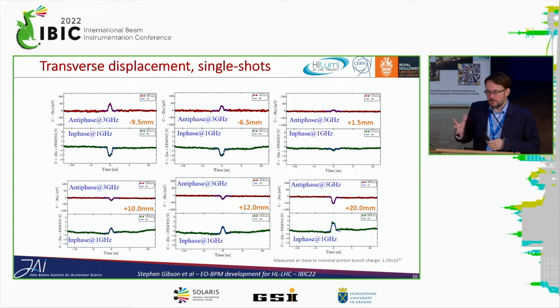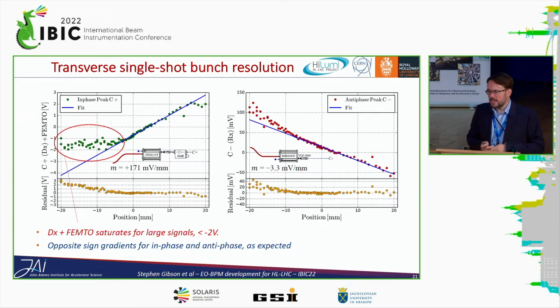As you get very close to the pickup, you actually start to see signs of effectively saturation, where the bunch is causing such a field inside the pickup that it's causing an over-rotation of the transfer function. So this is why it's distorted at the very last one, because we've got almost too much signal for what we want. And indeed, you see that saturation if you go even further or use a much higher bunch charge. So in this case, if you follow the linear region too far, then you start to saturate the amplifier here. So we've got, in this particular case, too much signal, and it's saturating the amplifier that we had in this particular system. Okay.